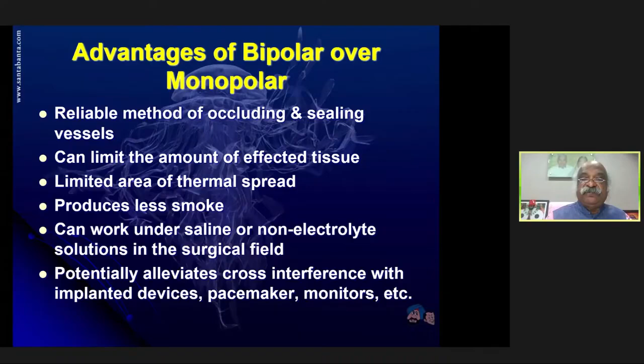Now, what do you mean by advanced bipolar? Advanced bipolar is otherwise known as a vessel sealer. The principles are high power but low voltage. Remember, it's a very low voltage but high power. And in addition, mechanical compression of the tissue and coaptation of the tissues occurs. By the instrument, you just grasp it, and mechanical compression of a vessel, what does it cause? The fluid will not be there.